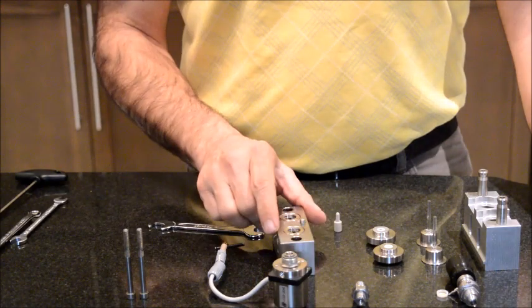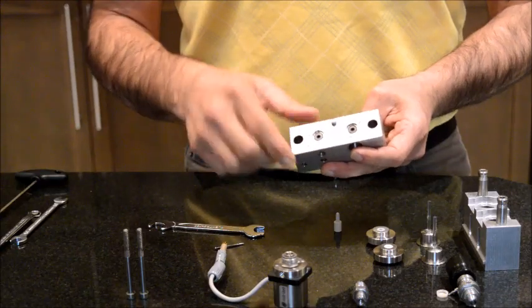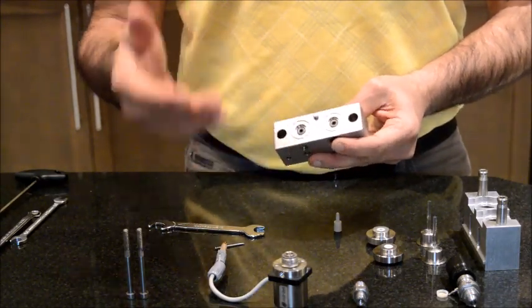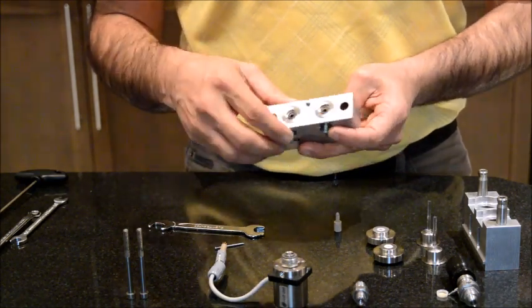If you want to use high concentration of THF you should go to metrology and tell them to replace these pump seals with the THF compatible pump seals so they will make your HPLC THF compatible. But these pumps are not meant for THF.